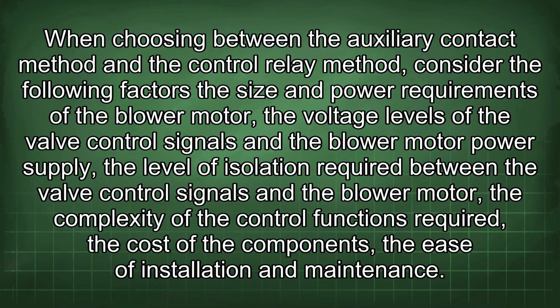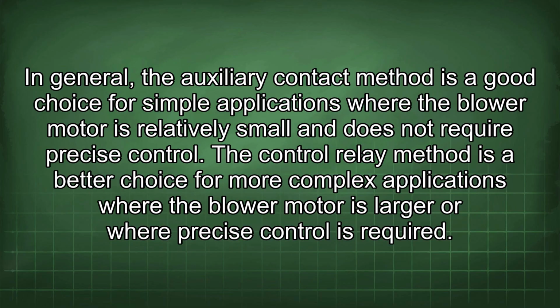When choosing between the auxiliary contact method and the control relay method, consider the following factors: the size and power requirements of the blower motor, the voltage levels of the valve control signals and the blower motor power supply, the level of isolation required between the valve control signals and the blower motor, the complexity of the control functions required, the cost of the components, the ease of installation and maintenance. In general, the auxiliary contact method is a good choice for simple applications where the blower motor is relatively small and does not require precise control.